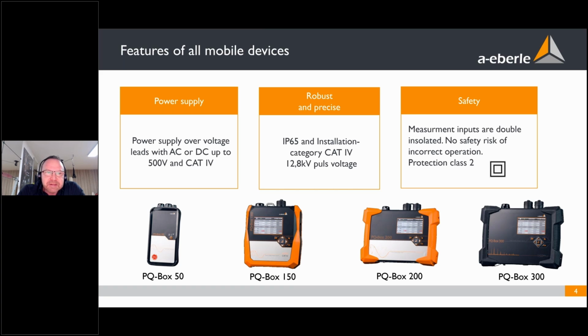If we install analyzers outside in the field, normally you do not want to use a socket, because it's more complicated. The easiest way is to supply the device directly from the voltage connector of your voltage leads, and therefore it's a must that the internal power supply should also withstand the highest transients. So we can supply all of our analyzers with any AC and DC voltage from 100 volt up to 500 volt. So it's really easy to connect them. All of our analyzers are waterproof, IP65, and for installation in the highest category, Cat 4, so you can easily measure directly at the transformer.